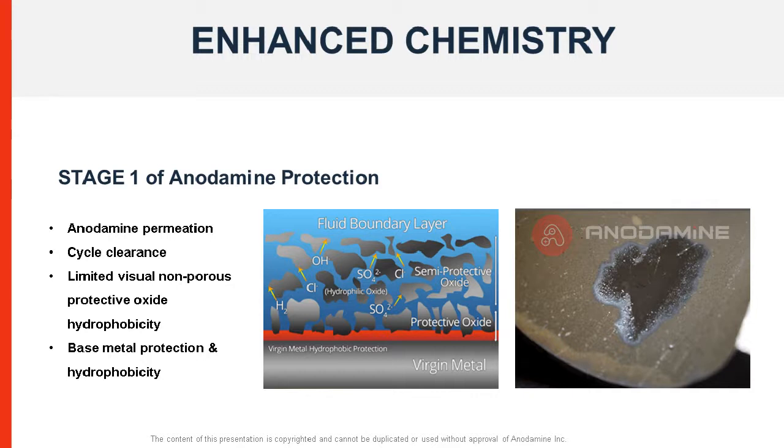During this process, the inorganic impurities are forced out of the porous oxides, which can lead to a temporary increase of cation conductivity. This phenomenon is called cycle clearance, and the increase of cation conductivity is not caused by anodamine, but due to its effect. The duration of the cycle clearance depends on the thickness of the oxides in the system and the amount of impurities within these oxides.